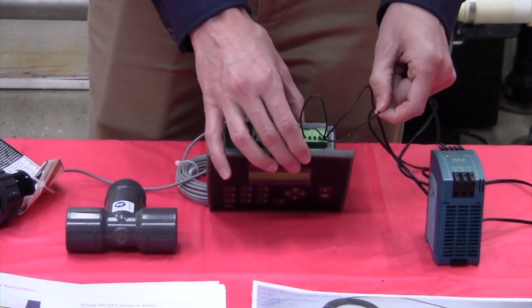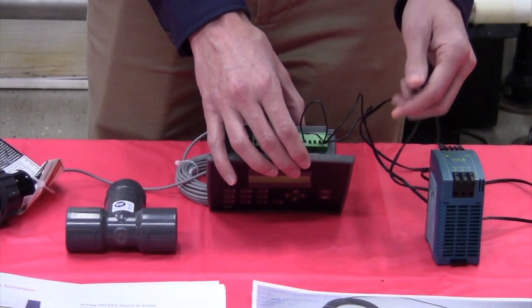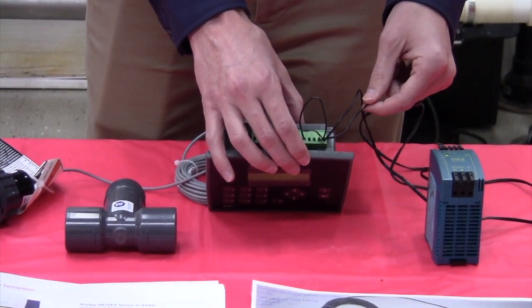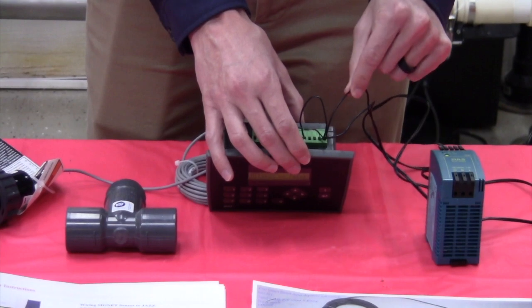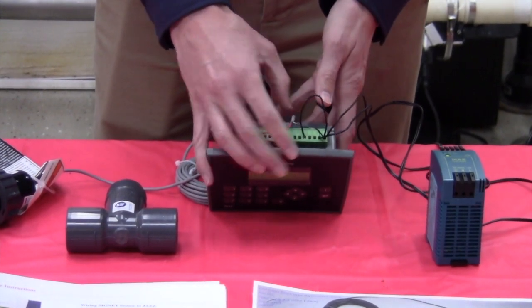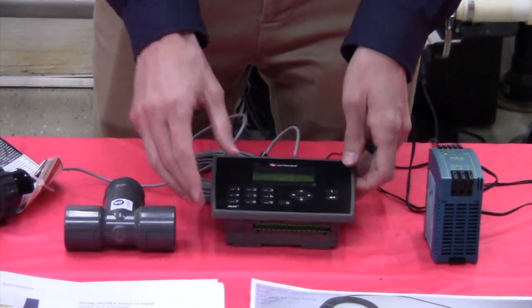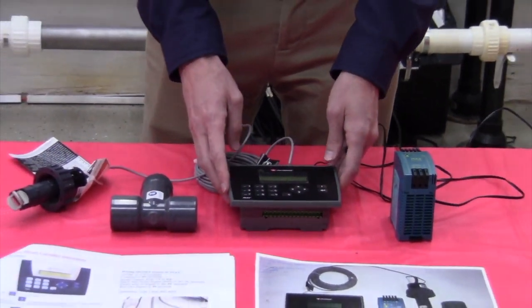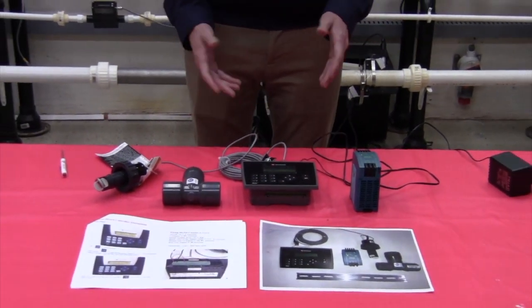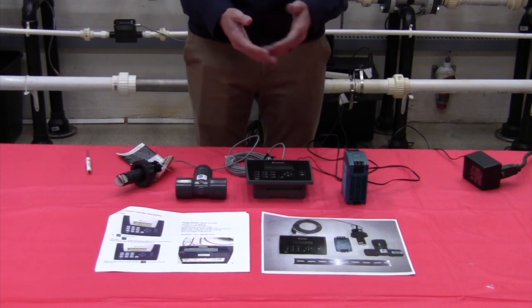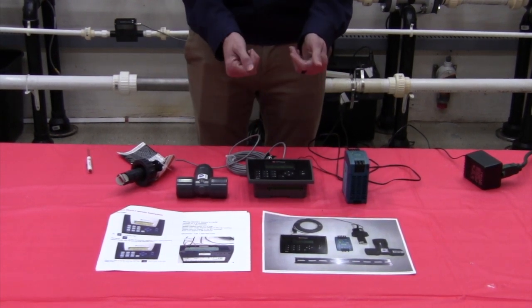One of the leads coming off the Triad power supply has white stripes on it, and that's the lead that goes into terminal 1. The solid black conductor is the one that goes into terminal 2. Again, all of that is covered here in the documentation. So now that I've done that, my display is powered up.